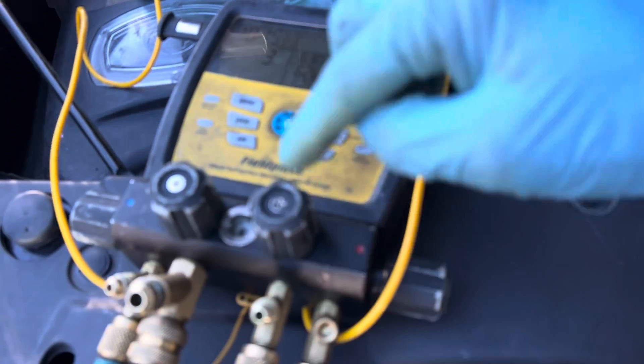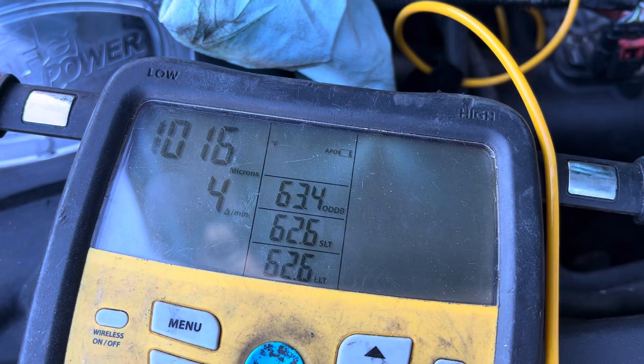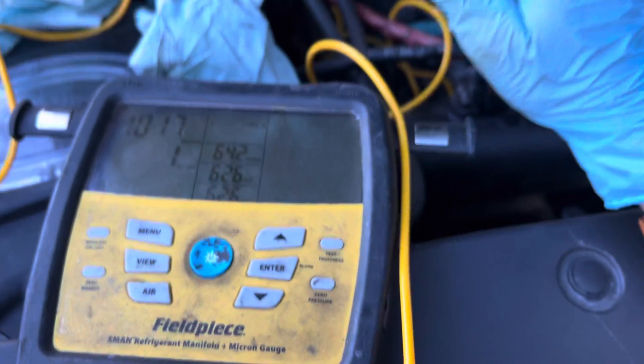I've been pulling this thing under a vacuum for quite a while. Right now I have the vacuum off and I'm letting it go through a vacuum decay. As you can see, it's stopping solid at 1016 microns and it's basically not moving. But vacuum is a very poor method to look for a leak, and that's why you resort to nitrogen.